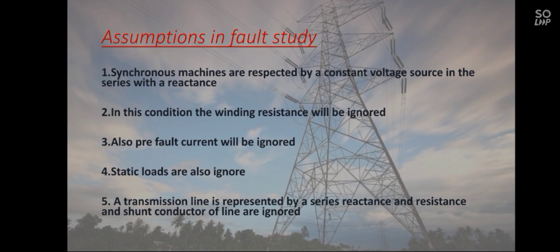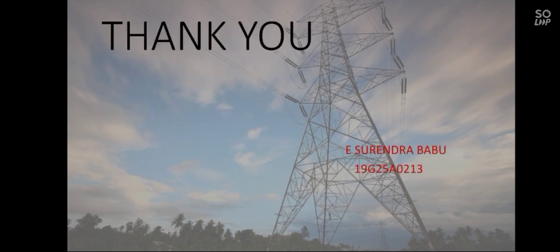Assumptions in fault studies. Synchronous machines are represented by a constant voltage source in series with a reactance. In this condition, the winding resistance will be ignored. Also, pre-fault current will be ignored. Static loads are ignored. A transmission line is represented by a series reactance and resistance, and shunt capacitance in the line is ignored. Thank you.